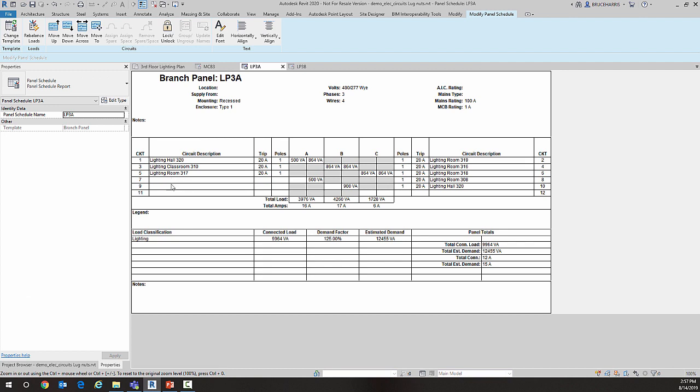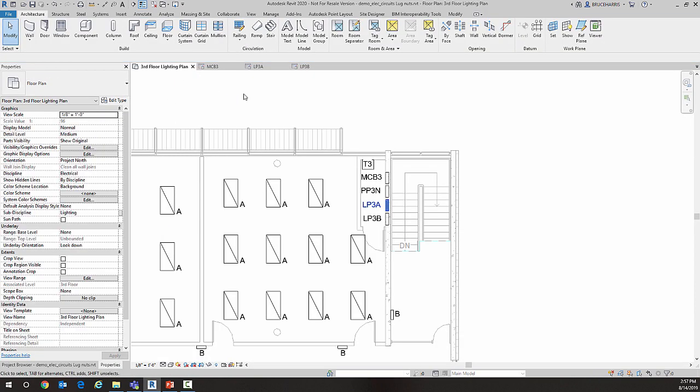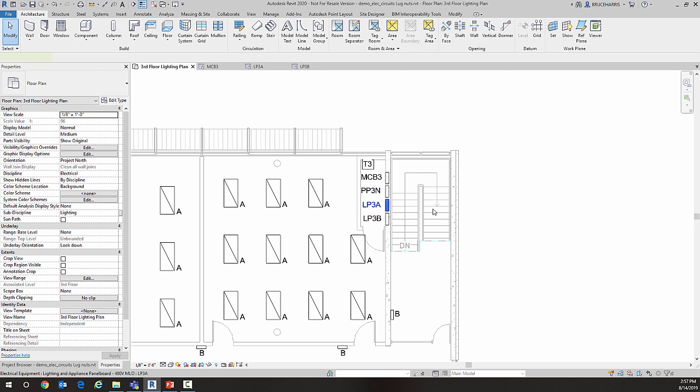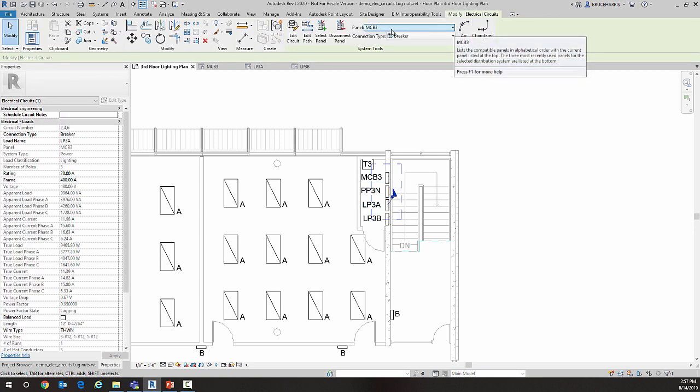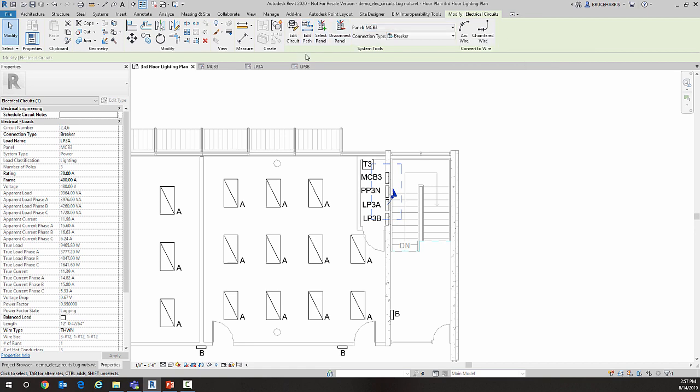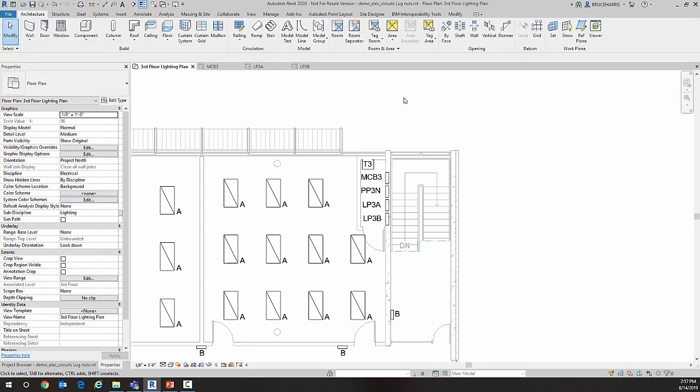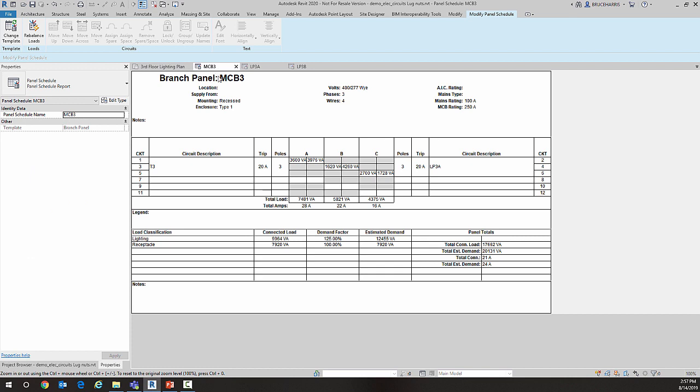Now if I were to connect LP3A—let me go ahead and make it go into MCB3. Let's look at the panel schedule. I have not only my transformer but also LP3A, and it has the entire load of the two panels that were fed together with feed-through lugs.